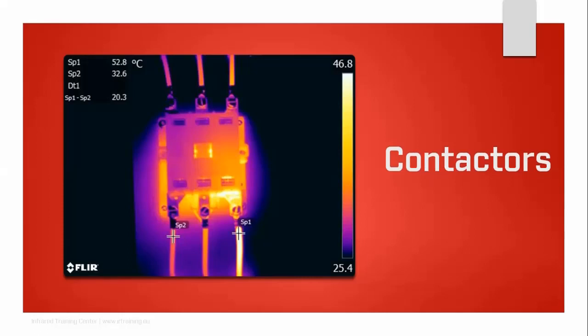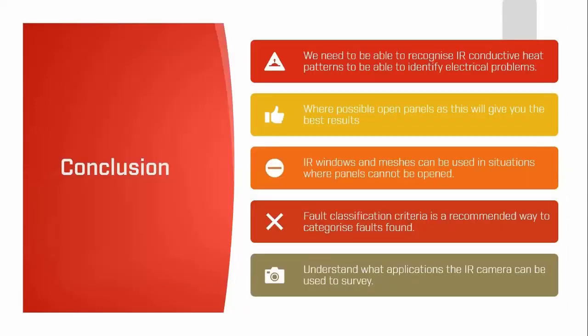To conclude: we need to recognize IR conductive heat patterns to identify electrical problems. Where possible, open panels for best results. Infrared windows and meshes can be used when panels cannot be opened — but remember to compensate for transmissivity as IR windows are not 100% transmissive. Fault classification criteria is a recommended way to categorize faults found — you can also create your own if you're competent enough. Understand what applications the IR camera can survey, and don't be afraid to look around during your survey.